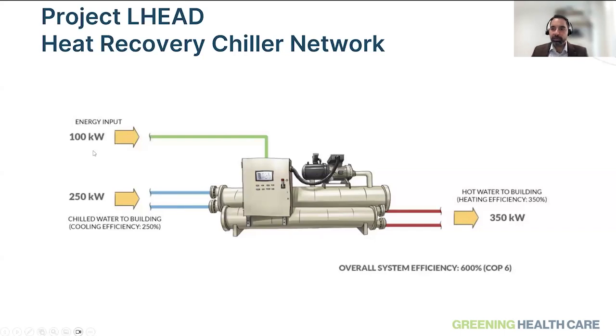So the concept of a heat recovery chiller is that it not only provides you hot water on one side, but it also provides you cold water as well. So if you put 100 kilowatts of energy into the heat recovery chiller, you get 250 kilowatts of cooling energy back into the building. And then you also get hot water, 350 kilowatts, which is being used as hot water in the building. So overall, you get a better combined COP than a traditional centrifugal chiller, because the application of this is to produce cold water and also to produce hot water, which is used in the building.